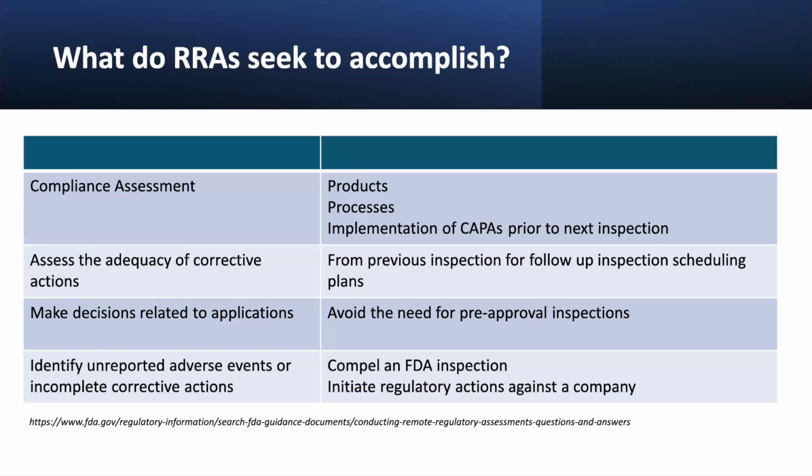So what I'm proposing to you is to make sure that your corrective action program is complete. It's well under control, because this is a low-hanging fruit area where the FDA is going to say, okay, if we were to do, and I'm thinking like a one-day remote inspection, right? So a supervisory investigator may say, do we need to do this inspection?